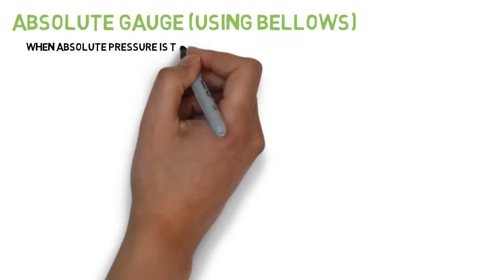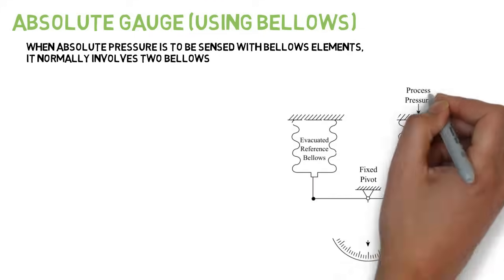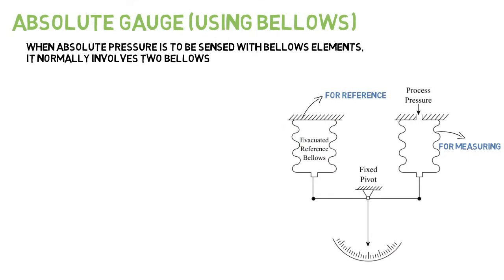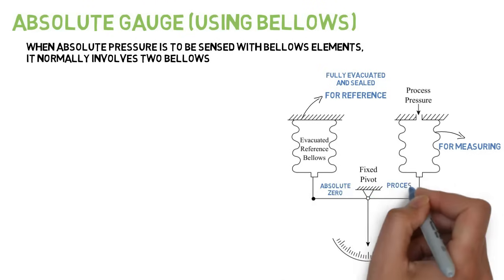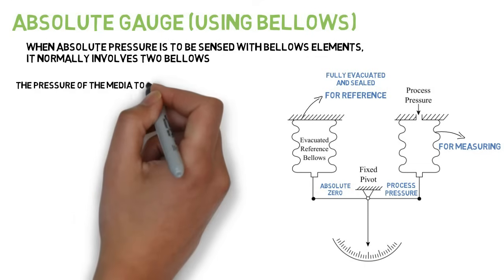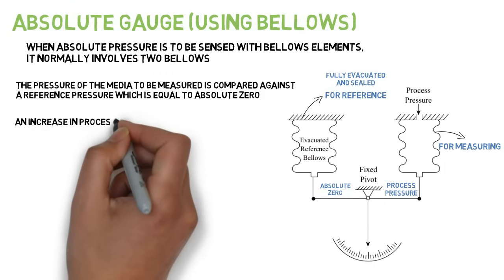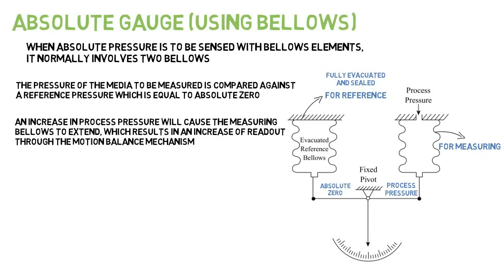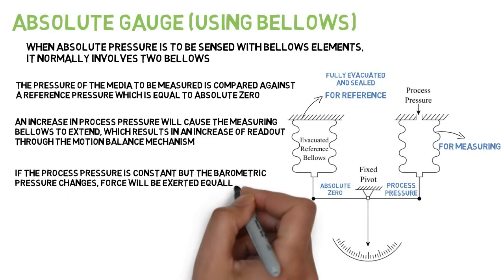When absolute pressure is to be sensed with bellows elements, it normally involves two bellows — one for measuring and one for reference. The reference bellows element is fully evacuated and sealed, while the sensing element is connected to the process. The pressure of the media to be measured is compared against a reference pressure equal to absolute zero. An increase in process pressure will cause the measuring bellows to extend, resulting in an increase of readout through the motion balance mechanism. If the process pressure is constant but the barometric pressure changes, force will be exerted equally on the outside of both bellows, causing no change in the readout.